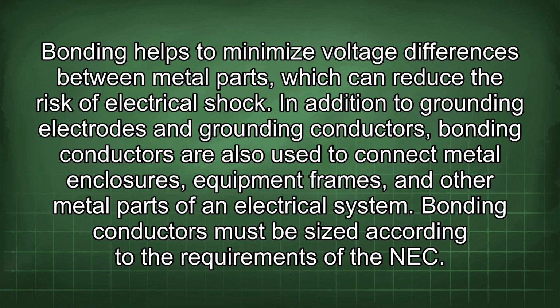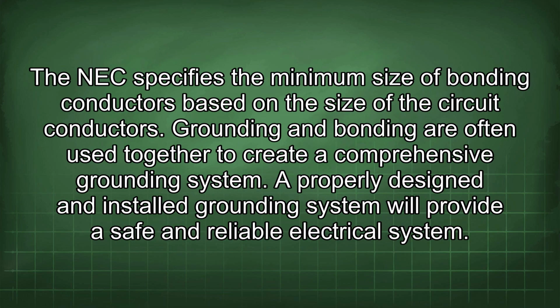In addition to grounding electrodes and grounding conductors, bonding conductors are also used to connect metal enclosures, equipment frames, and other metal parts of an electrical system. Bonding conductors must be sized according to the requirements of the NEC. The NEC specifies the minimum size of bonding conductors based on the size of the circuit conductors. Grounding and bonding are often used together to create a comprehensive grounding system. A properly designed and installed grounding system will provide a safe and reliable electrical system.